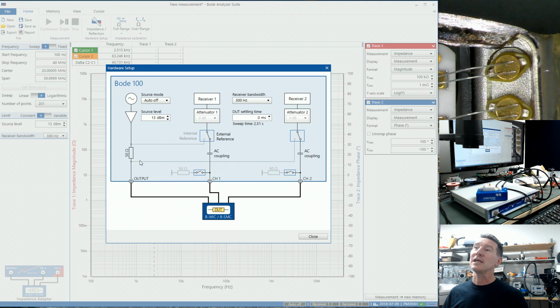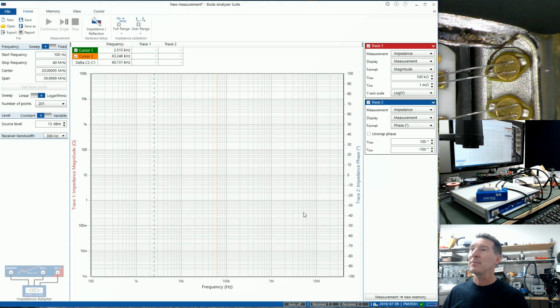Anyway, you can see that the internal output path here can measure the internal reference, and the receiver too can do that. There are two receivers inside, so that's how it can get the S11 reflected power, the reflected measurement coming back. So anyway, you can set all that stuff up. So we've got our cursors. So let's go from 100 hertz. Let's go over the full range, shall we?